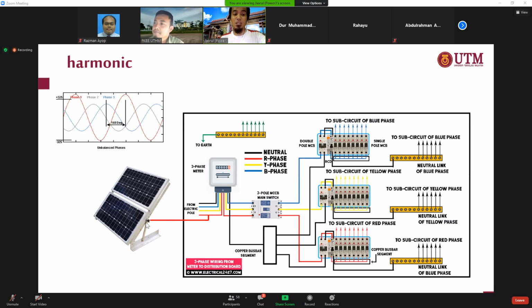Here's the idea: for example, let's say you are not at home, all of you go to your hometown, so there's no load at all, you switch off everything, so there is no demand. But suddenly you get injected power from the PV during the noon. This injected power goes to the single phase, and what will happen? It might cause one of your phases to have voltage higher than the limit, which causes over voltage.